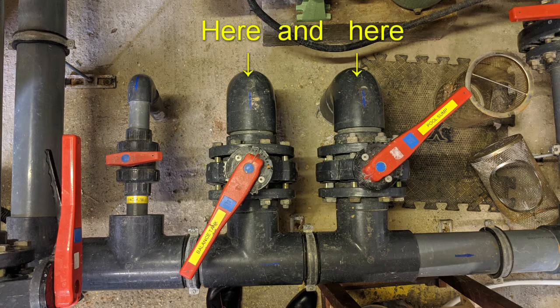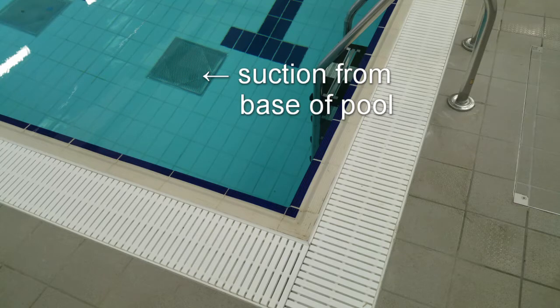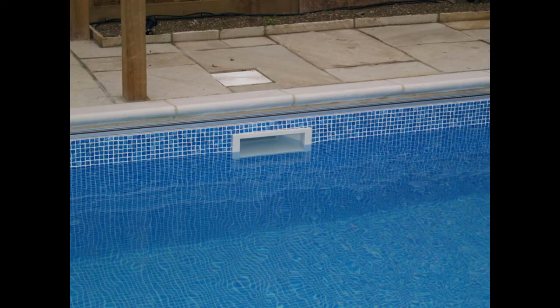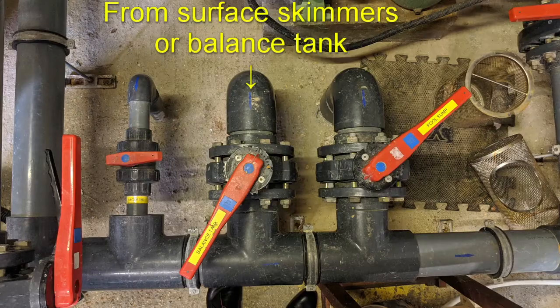What these two pipes are is, one of them will be the pipe that's basically drawing water from the base of the pool, from the pool sumps. The other one will be the pipe that's bringing water in from the surface water draw-off system. So if you've got a skimmer basket pool, for example, those skimmer baskets will have pipework that will usually join up to form one common pipe, and that's the pipe that you're seeing coming into the plant room directly from the skimmer system, the skimmer basket system.